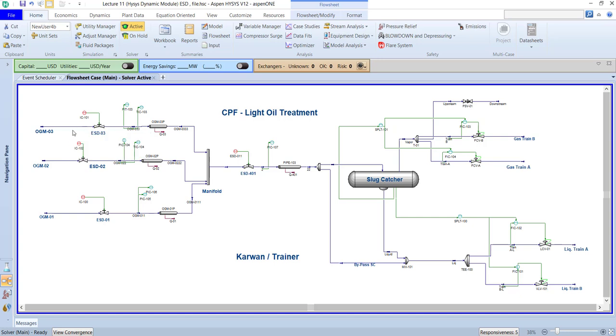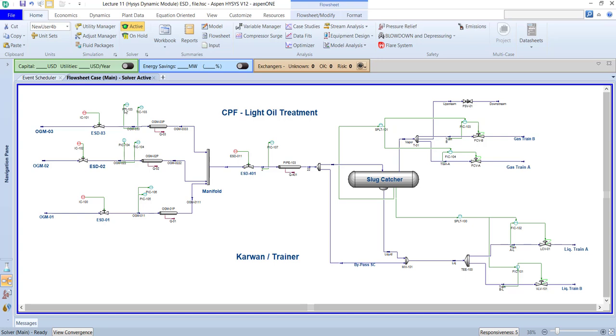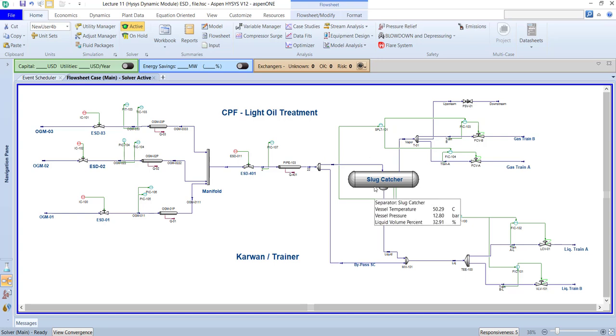Normally the pressure inside the OGM main line is around 12 to 13 bar. But when the pressure reaches, for example, 20 bar, that creates a problem because the pipeline design is not rated for 20 bar. For that reason we must protect our system. If the pressure indicator reads 20 bar, it directly sends a signal to the ESD, which immediately shuts the line to protect it — because pressure may increase due to an issue downstream of the slug catcher, or because a manual valve on the line is closed.